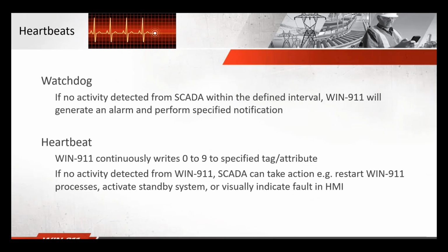So heartbeats are similar to a watchdog. Watchdogs allow Win911 to generate alarms and perform notification out if no alarm activity is detected from the SCADA. And so we have this communication channel between Win911 and the SCADA package. If something stops flowing across that channel, then the idea is that we won't detect activity on a defined point, and that will set off a timer which will generate an alarm.